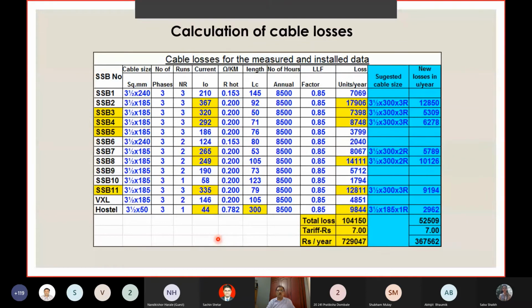See, if you know in a day, if there are 1 lakh units consumed by that industry, 6% means 6,000 units going as loss in the distribution cables. 1% means 1,000. It is desirable to minimize the losses to, let us say, middle of the way. 3% means you will have a saving of 3,000 units per day.